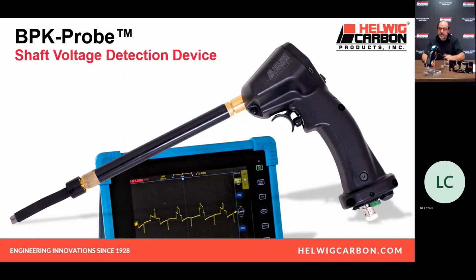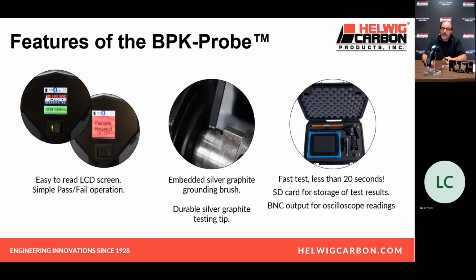And that just takes seconds by pressing the tip of the probe against your motor shaft. What does the tool feature? It features a number of display test results. Very simple, very easy to read. It'll tell you if your bearing's passing or failing. It'll tell you if you have a ground fault. It checks for grounds. It'll tell you if you're passing, but just barely, with a yellow indicator.